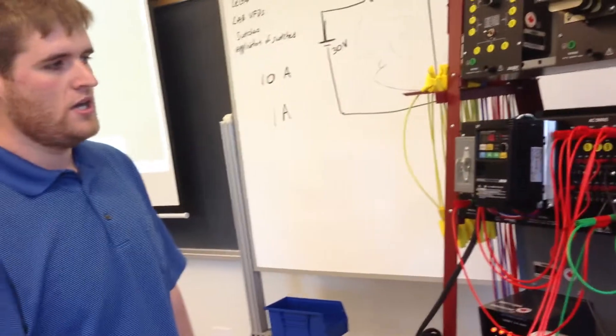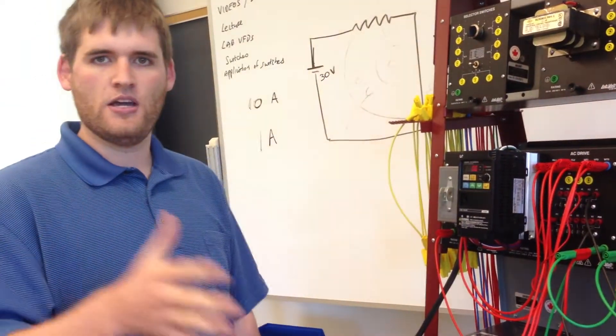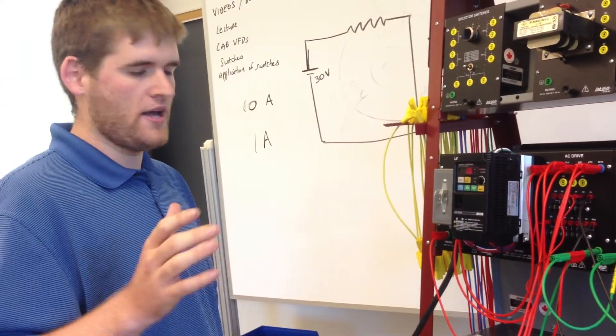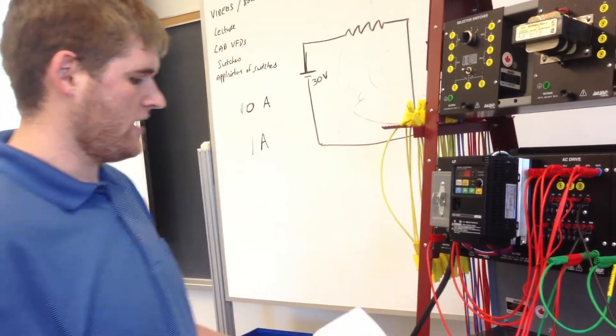So basically what the overload limit functions provide for is so that we can set it so that once it hits a certain current it's going to scale back the speed of the motor to stay at that current so that we don't burn up motors. So there's a couple of different parameters you can set involved with that.